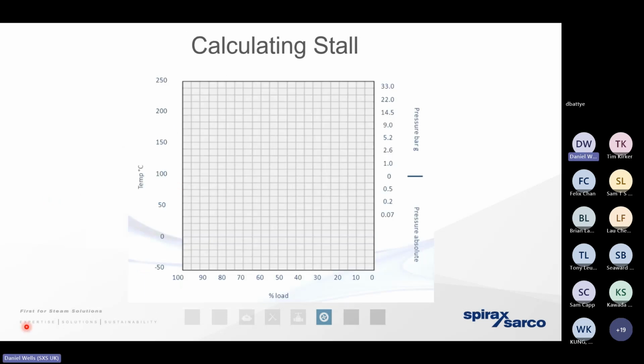So we can calculate the likelihood of stall occurring by going back to what we call a stall chart. You remember in previous presentations that we've got that pressure temperature relationship with both steam and condensate. So we can plot both the pressure and the temperature on this curve. For example, if I choose 100 degrees, you'll notice that the temperature is exactly the same as the pressure. 100 degrees, 0 bar gauge.